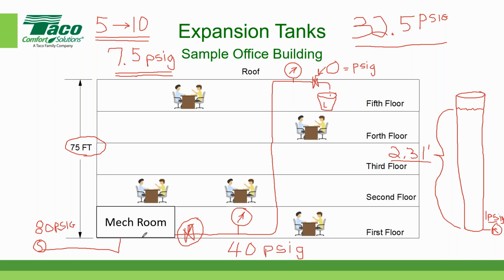And initially, all I did was open up this manual valve here to allow my piping system to fill. When I got a couple of drops of water out, I closed this valve, and then I closed the valve at the top. And so I isolated myself from my pressure regulating valve. And so the only pressure I had was the function of the height of the fluid. Then I said I wanted to have not 0 pounds at the top, I wanted 7.5 pounds. So to achieve that, I kept this valve at the top closed, and I opened up this manual valve down here, and I watched my gauge very carefully until I got 40 PSIG.